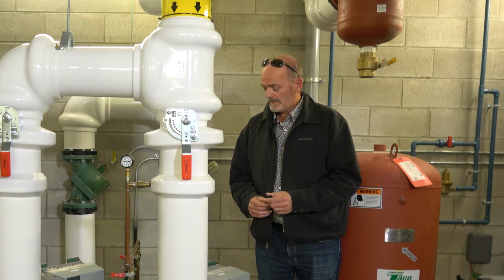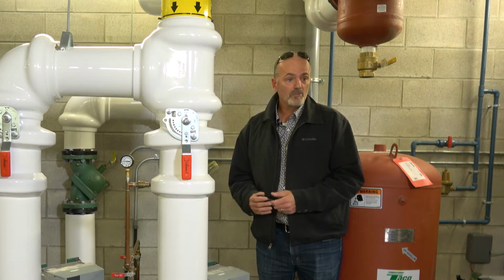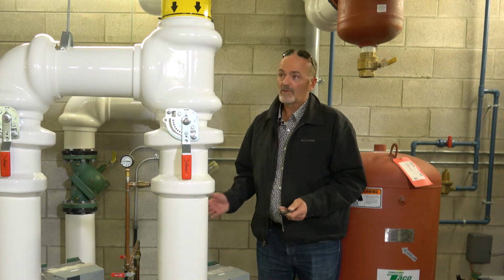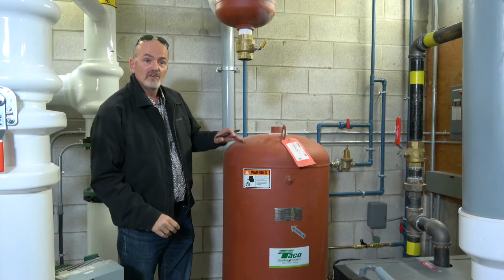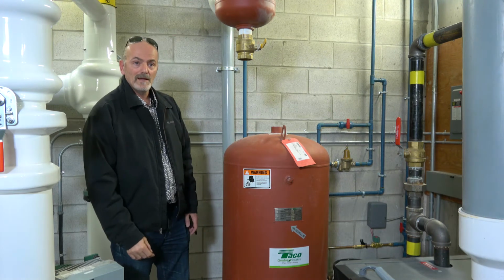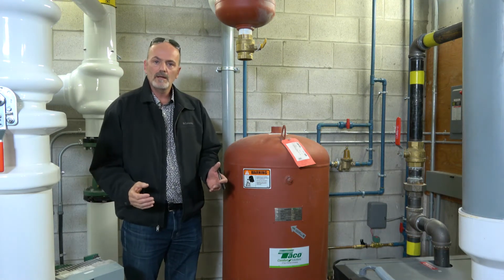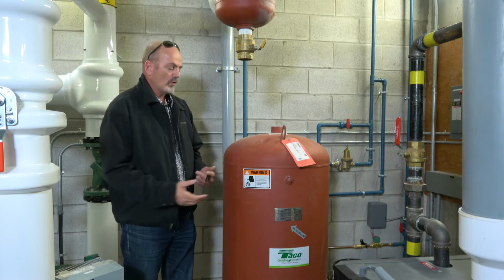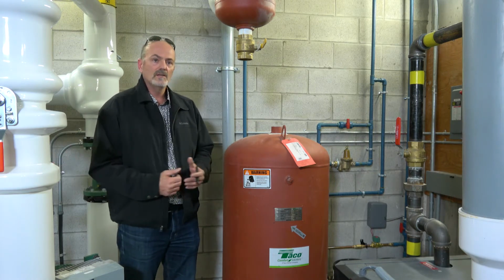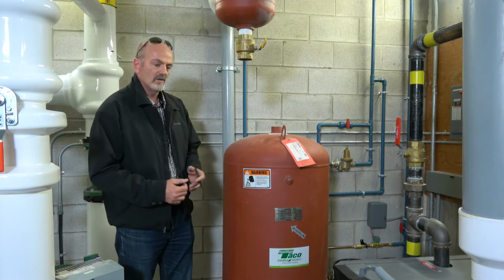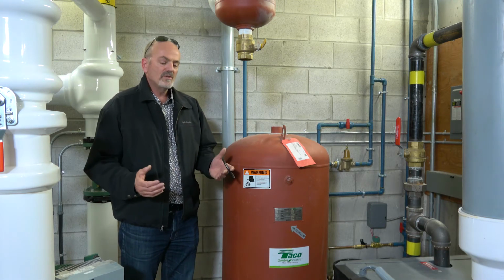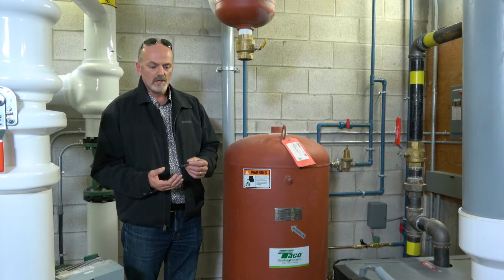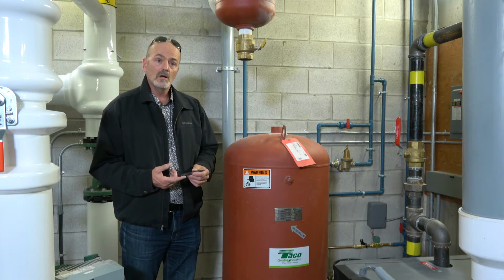Okay, and that's it for the vertical inline pumps with drives and their accessories. This is what's known as an expansion tank. Every hydronic and every chilled water system, and this will hold true for all the tanks in this mechanical room, so we'll just focus on this one.